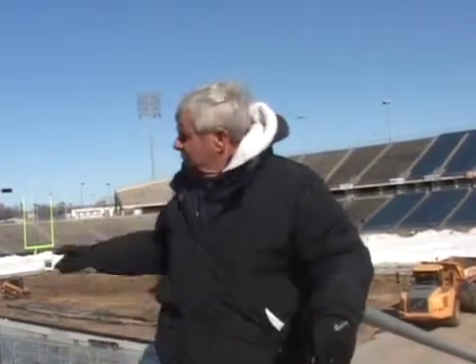So that's a concern, something we have to take a little precaution for. What happens then is the mat system comes in 6-foot sections. There'd be 15 sections, which would be a total of 90 feet. They all come built into a header, and each section is connected to the header with a fitting called a Victaulic fitting, which is a slip joint. You slip it over the two ends, they mate up, put a gasket on it, and then we connect them with these Victaulic fittings.